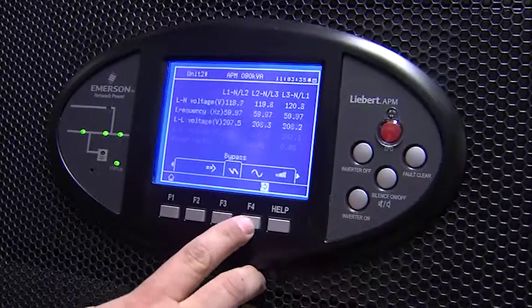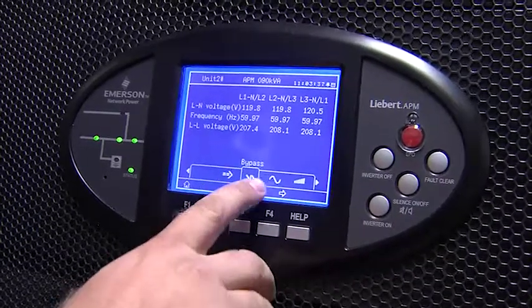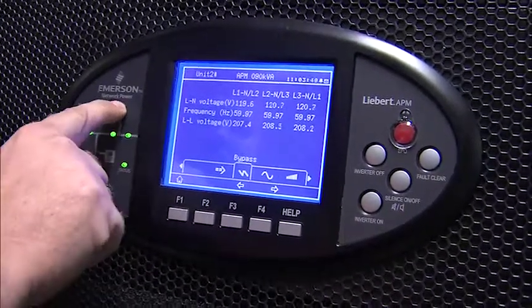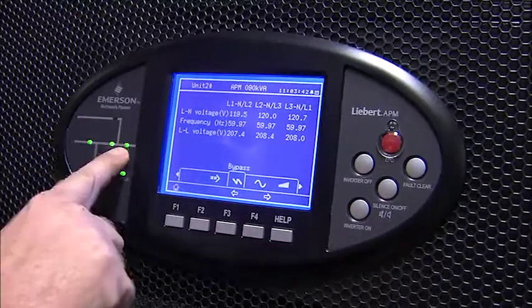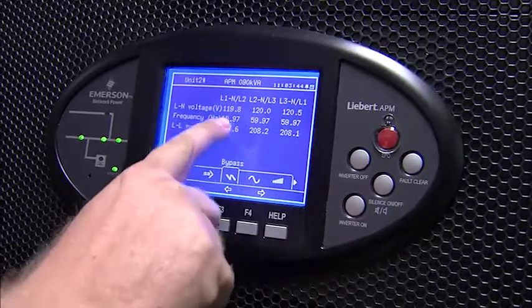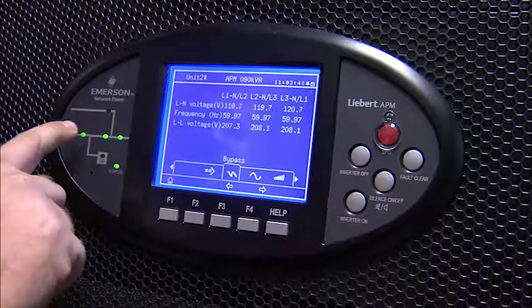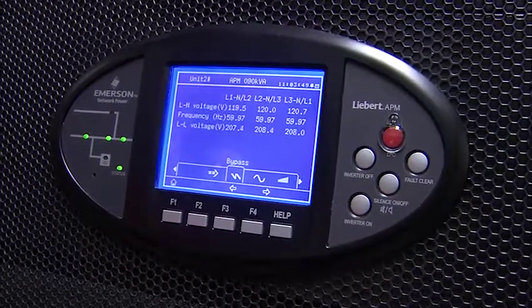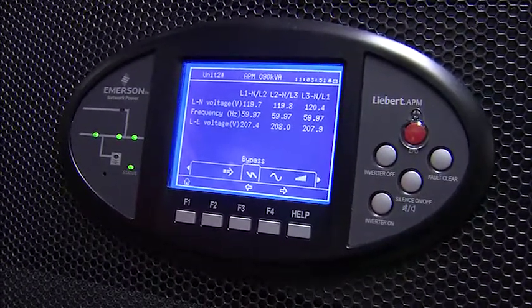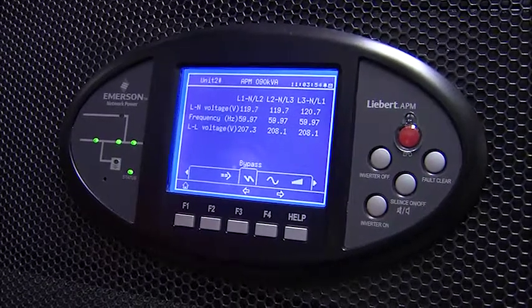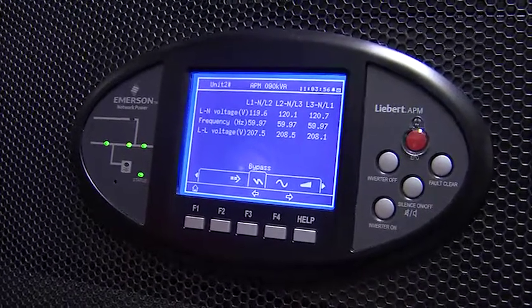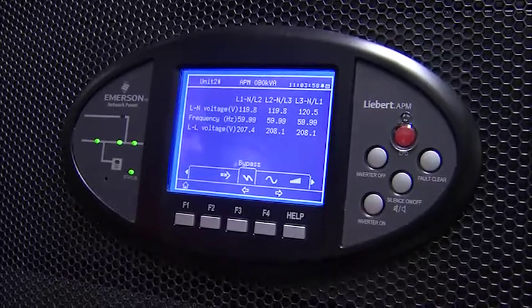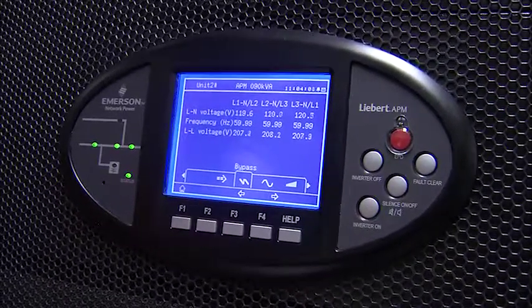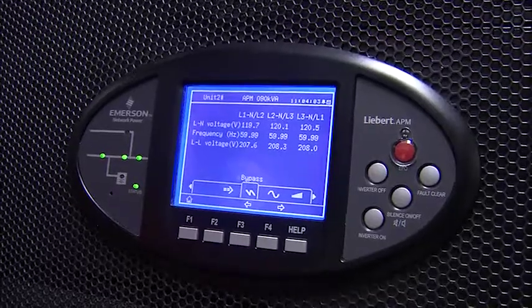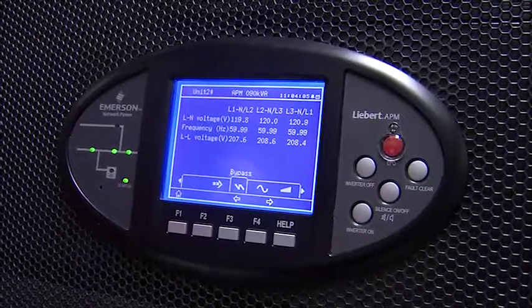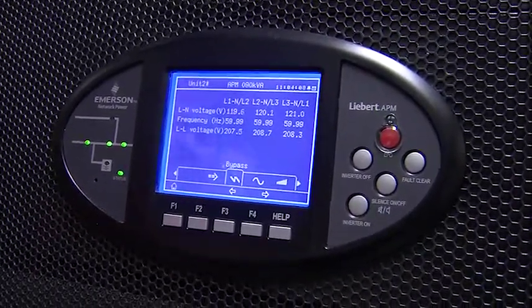Scrolling through, we now have our bypass voltages. So if we were to go to bypass, it synchronizes these bypass voltages with the input to make sure they're in sync to go to bypass. If for some reason they were never in sync, it wouldn't allow you to go to bypass. It would call out an asynchronization error. And typically 90% of the time, you wait a second and then it becomes in sync. It just depends if you have a generator running in the building or something's going on, but it will tell you that.